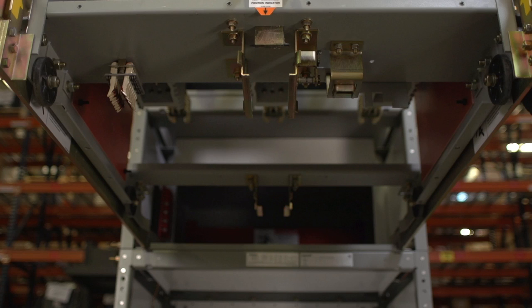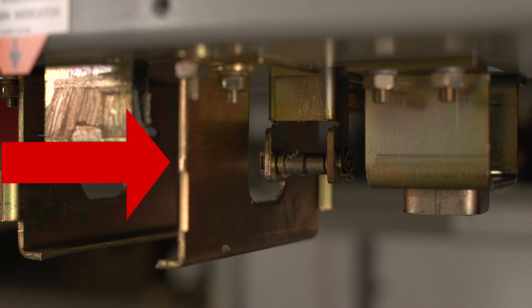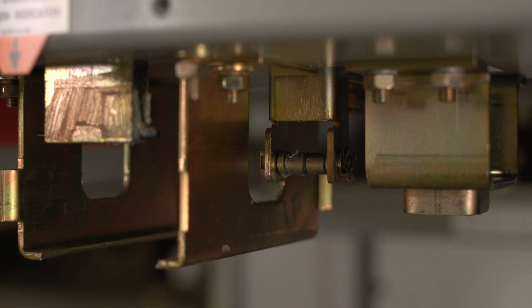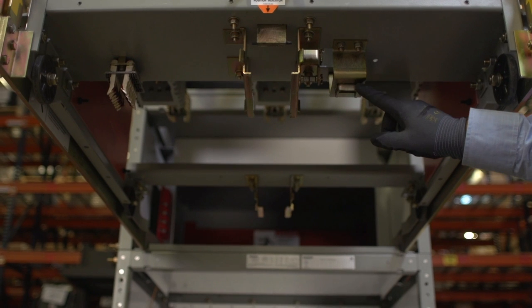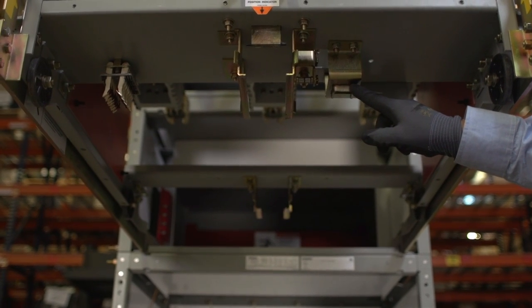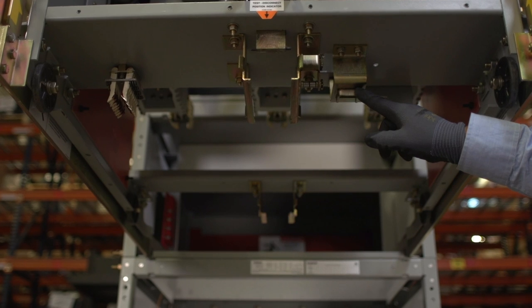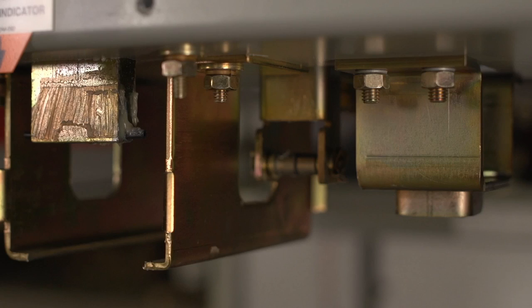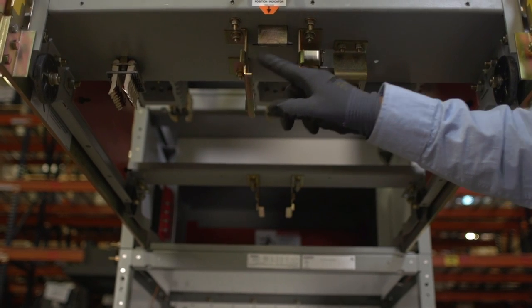Let's take a look at the important components found on the bottom of the circuit breaker. This is the trip-free interlock. It prevents closing the circuit breaker unless the circuit breaker is in either the connected position or in the test position. The trip-free interlock interacts with the sliding cam plate on the racking mechanism. This is the closed circuit breaker interlock. It prevents access to the racking screw when the circuit breaker is closed. This is the guide rail. It helps align the circuit breaker in the compartment. Here, we have the circuit breaker interference plate to help ensure an adequately rated circuit breaker is being inserted into the cell.